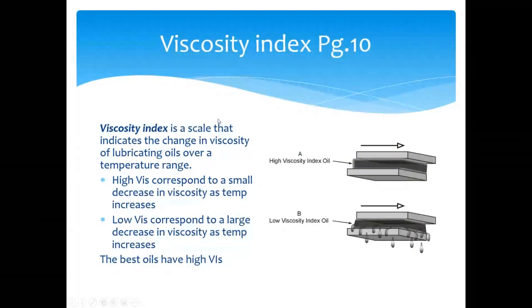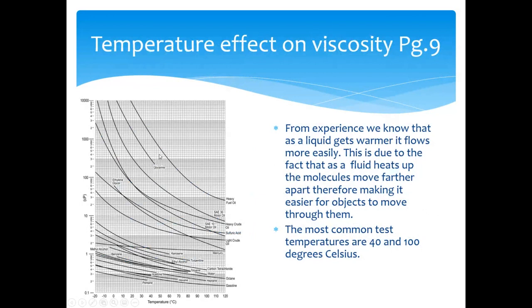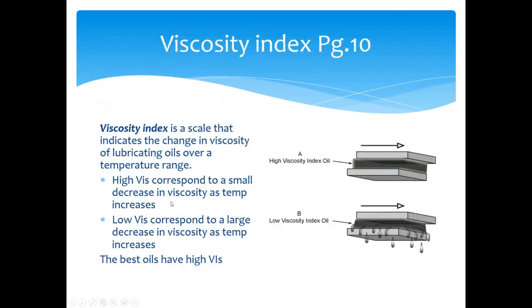A viscosity index is a scale indicating the change in viscosity of lubricating oils over a temperature range. A high viscosity index corresponds to a small decrease in viscosity as temperature increases; a low viscosity index corresponds to a large decrease. The best oils have high viscosity indexes, meaning they don't change much across a broad temperature range — a high viscosity index oil holds together much better than a low viscosity index oil at the same temperature.